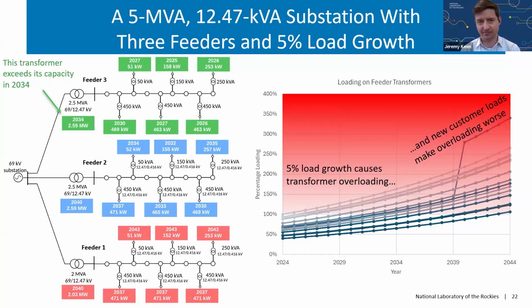Here I'm showing a test case available for people to use through the GDM loader. It's a 5 MVA, 12.47 kV substation with 3 feeders. On the right-hand side, you can see the loading on different transformers, showing the exponential loading that's happening. There are also new customer loads pushing these transformers further into the red, meaning they're way overloaded. The color boxes on the left show the year in which different transformers and lines exceed their capacity.